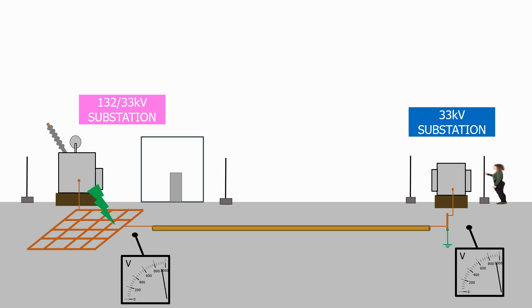How do we solve this problem? Well, the easiest way is not to connect the cable sheath at both ends. It is normal practice to only connect the cable sheath to the grounding grid at the source substation, and we will therefore not get any transferred potentials.